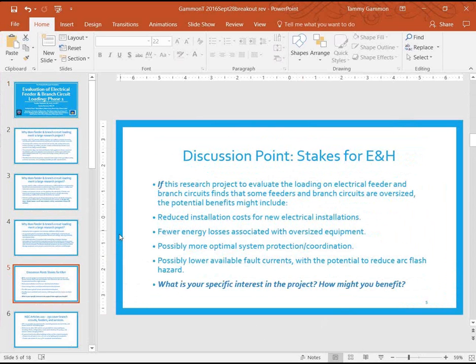Okay, well basically what I was thinking is we're going to be leading to right-sized distribution transformers and things like that. If the transformers are oversized, we're looking at higher potential fault currents than we need. If we reduce equipment size, we reduce the potential fault current a little bit. And as far as losses - if we replace transformers, especially according to the new 2016 requirements, we're going to be purchasing more efficient transformers.